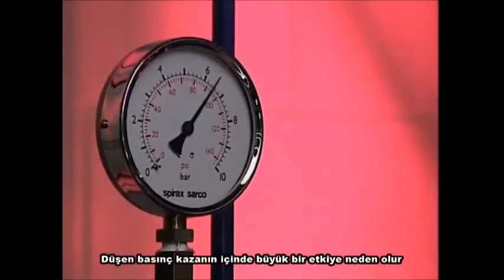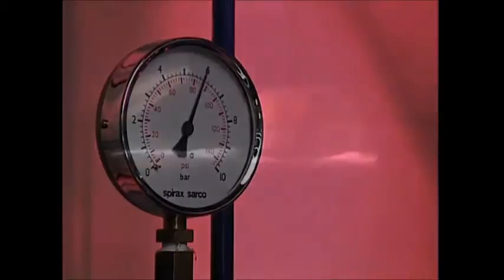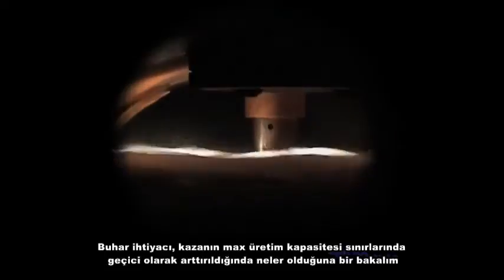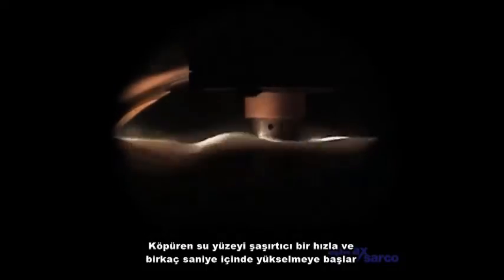Falling pressure has a major effect inside the boiler. Watch as the steam demand is temporarily increased, but within the boiler's maximum output capability. The bubbling water surface begins to rise with surprising speed, and within a few seconds, the level is so high that water and foam are being drawn into the steam takeoff. As soon as the high demand moderates, the pressure rises and the surface level quickly returns to normal as normal operations re-establish.